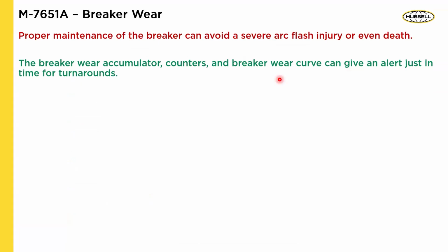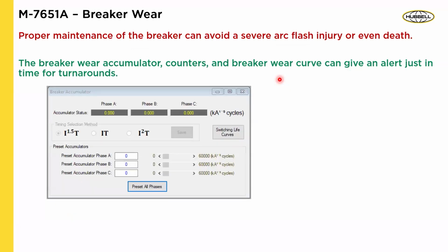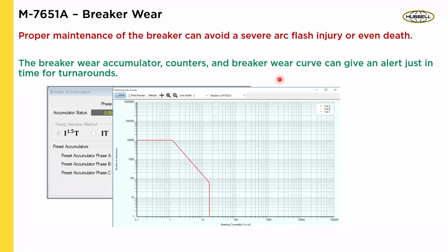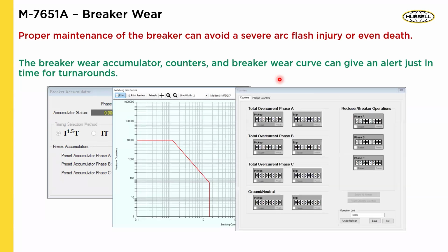And then we get into arc flash, which is when you want to avoid severe injury or even death in terms of arc flash, and you want to do breaker maintenance. So, well, we know that for the breaker accumulator you could do I square T, I 1.5 times T, and or IT. And then we plot that on the curve for the breaker. And then you also have the counters to go along with it. So you could get a better picture, a full picture of what your breaker's wear is. And you could set alarms and limits so that you can know when that limit has been reached, and you can schedule it for your next turnaround.